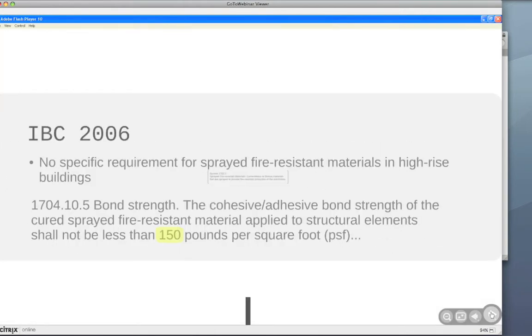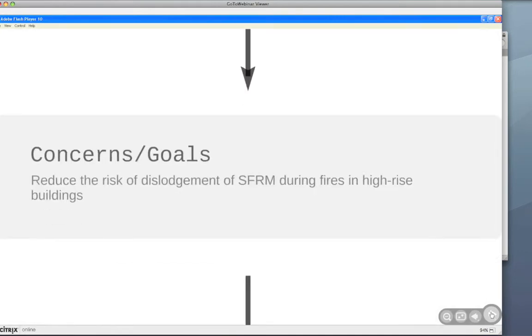A general bond strength requirement for all buildings was provided in IBC 2006, which specified a minimum of 150 pounds per square foot (PSF) for sprayed fire-resistant materials applied to structural elements. Now, a new requirement specific to high-rise buildings was added in IBC 2009 to reduce the risk of dislodgement of sprayed fire-resistant materials during fires in high-rise buildings, which are essentially high-risk fires.